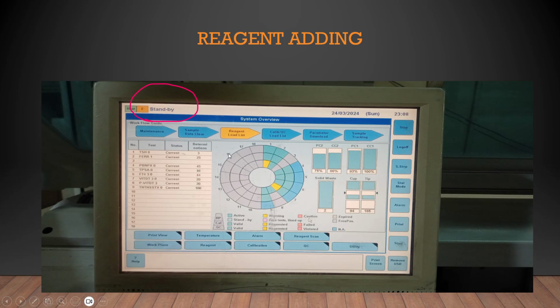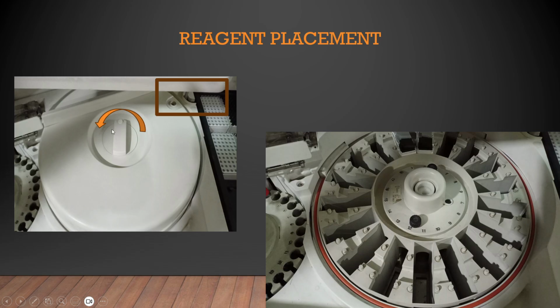So once the instrument is in standby position, you can remove the reagent disc cap. Okay, so you just have to rotate it like this. When you are taking it out, make sure that this area is secured. Now this is very important because many times I have seen that the mixer probe is also present here. Many of the technicians will touch this cap to the mixer probe, and because of that the mixer probe may get bent. Okay, so it's very important that you lift it carefully outside. Once you lift it outside, this is how the reagent disc looks like.